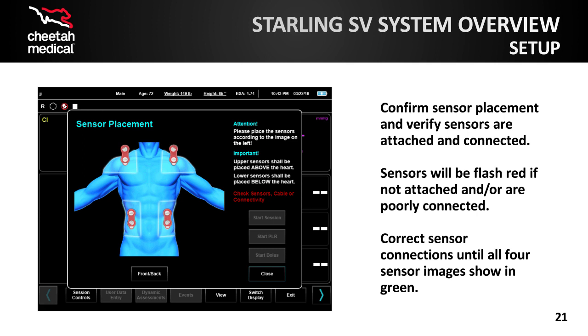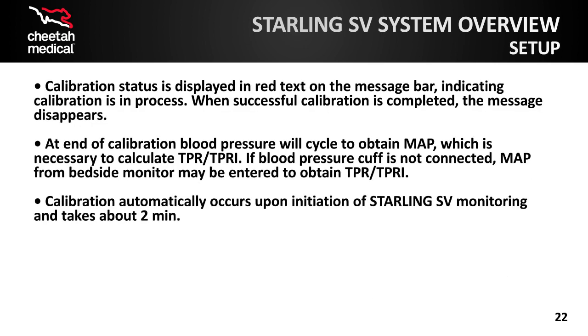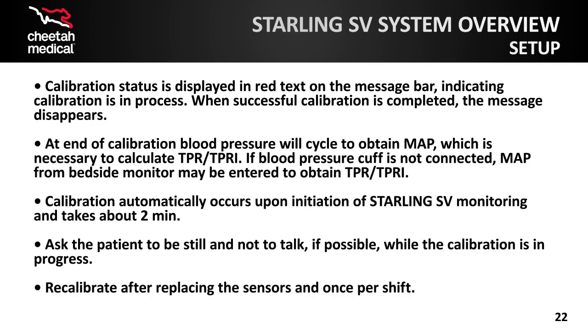Correct the sensor connections until all 4 sensor images show in green. Calibration automatically occurs and takes approximately 2 minutes after selecting the Run button on the touchscreen to begin Starling SV monitoring. Ask the patient to relax, remain motionless as best as possible, and not talk during calibration. A red bar appears at the top of the screen indicating that the calibration is in progress.